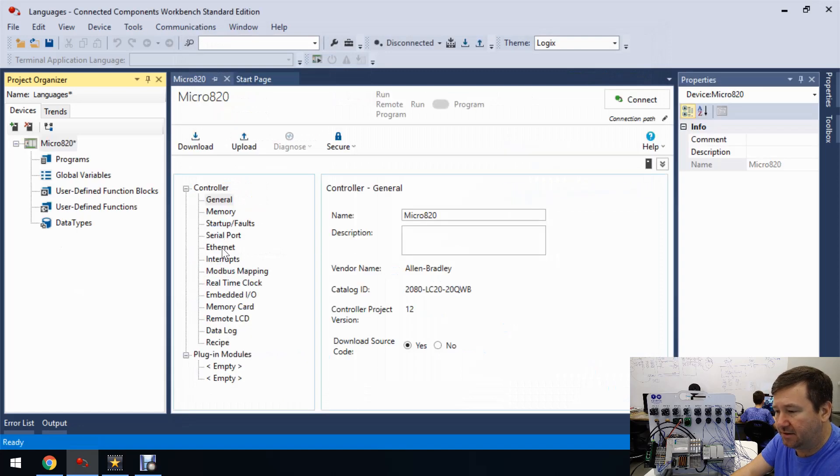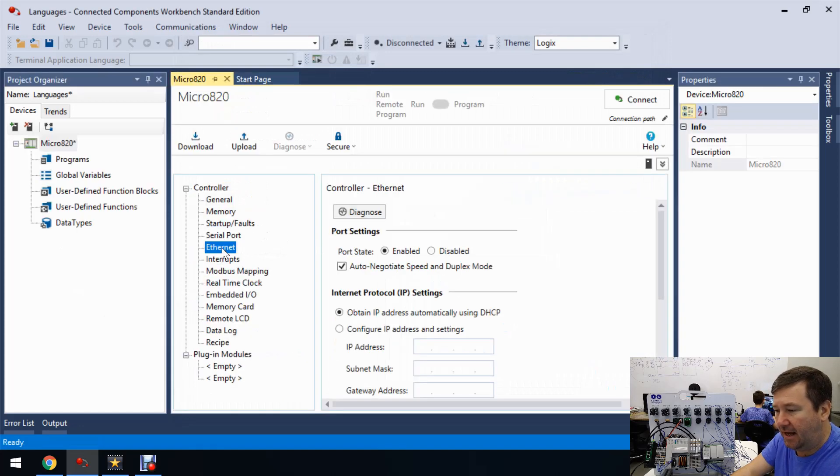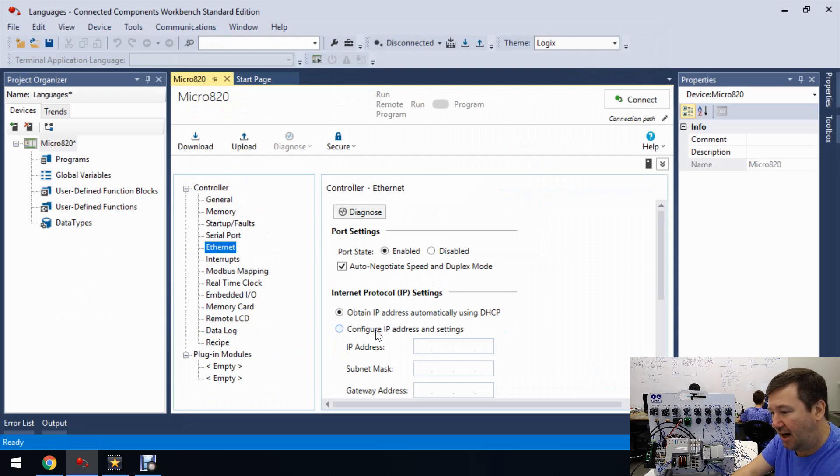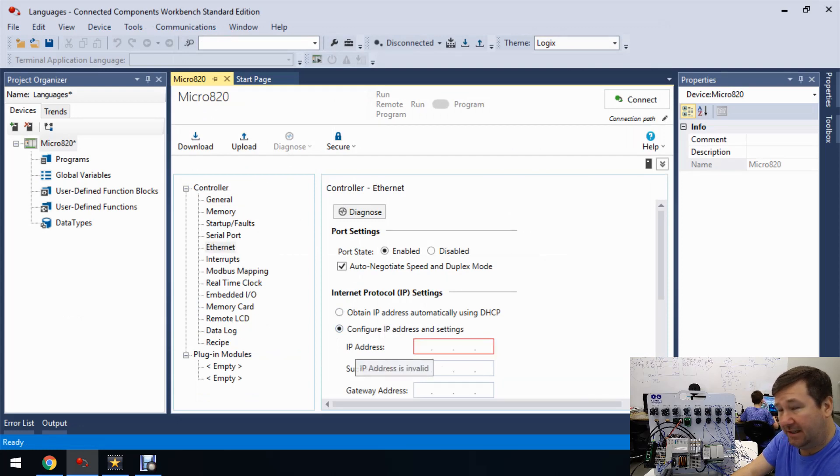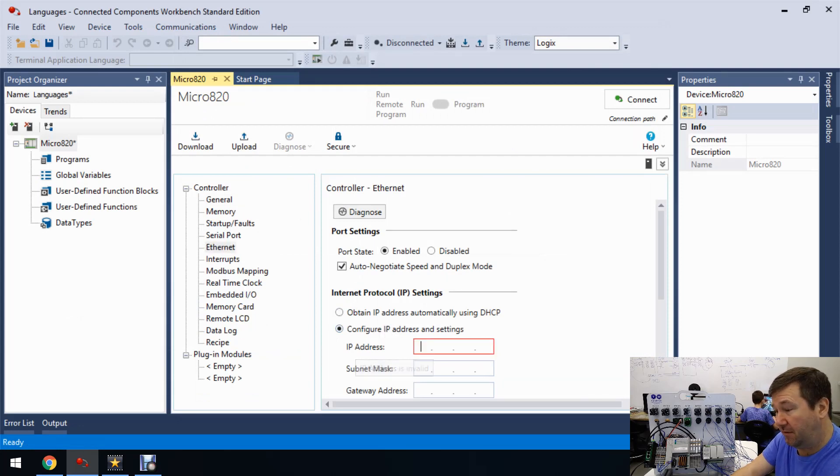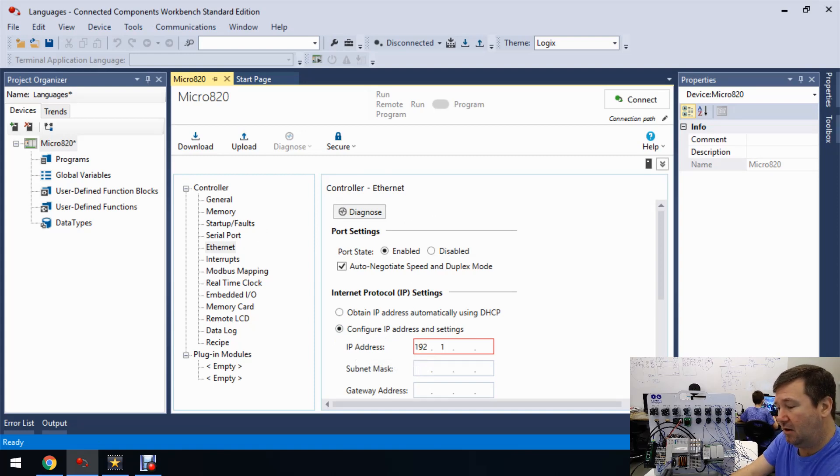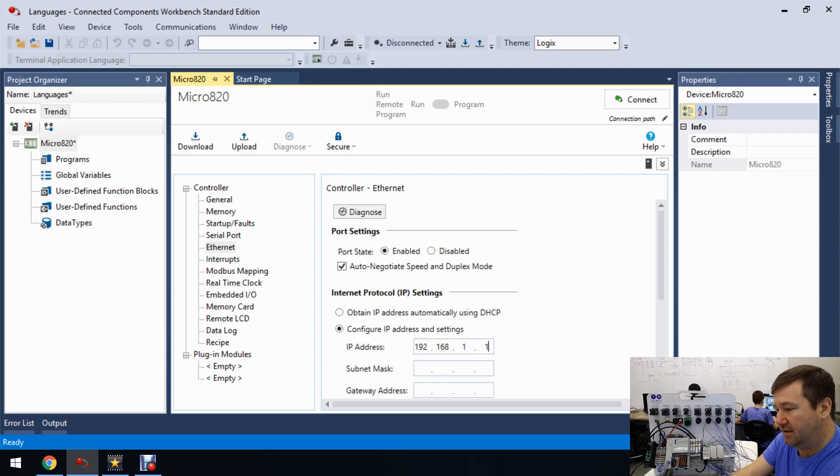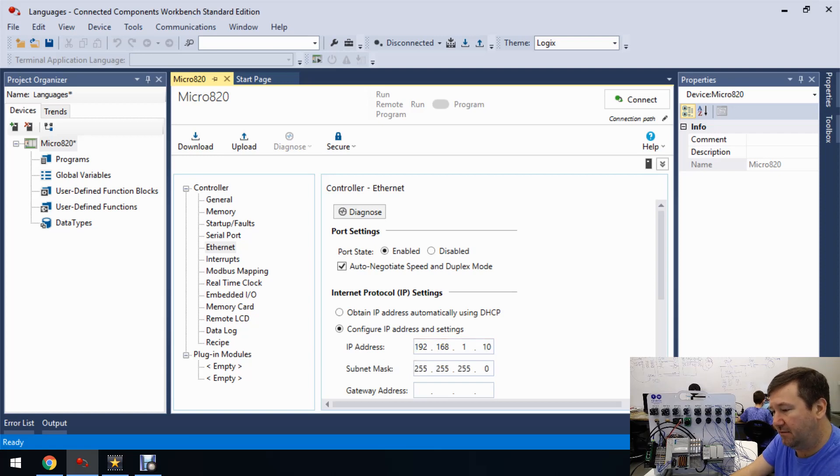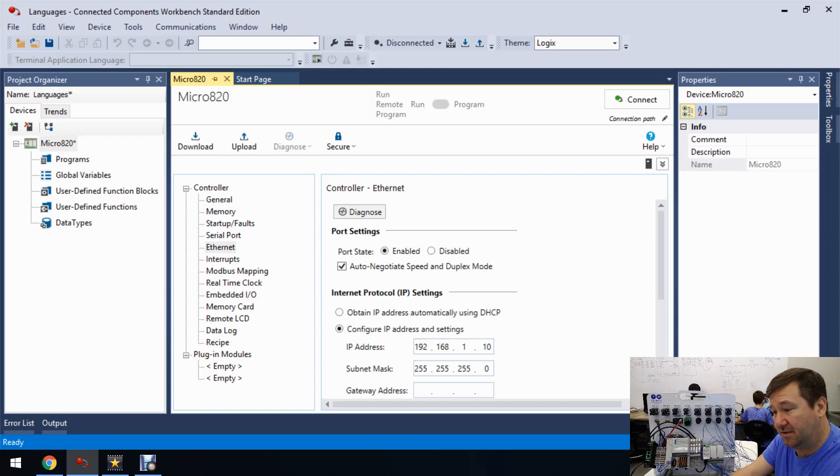And first thing, let's go ahead and add our Ethernet configuration because this is the most common thing I get a call about is people downloading programs without their IP configured and can't get back online with it. So it's going to be 192.168.1.10 with a subnet of 255.255.255.0.